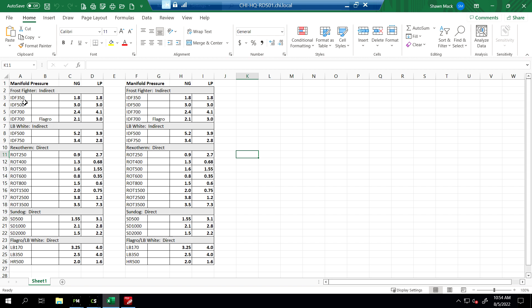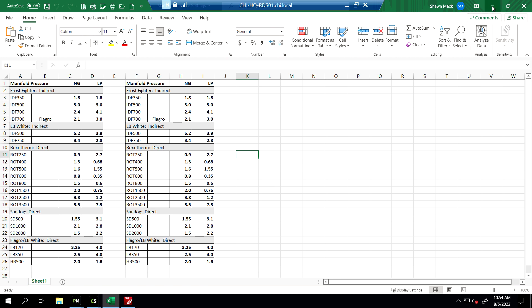If this was an ROT 250, we put it at 0.9 inches on natural gas, 2.7 on propane. We've got these little cheat cards in each one of our bags. They're good reference numbers to get us to about the temperature that we want to set the heaters for. If you want to set for temperature instead, go ahead and set for temperature. And that's the information that we're putting into the gas pressure and temperature.